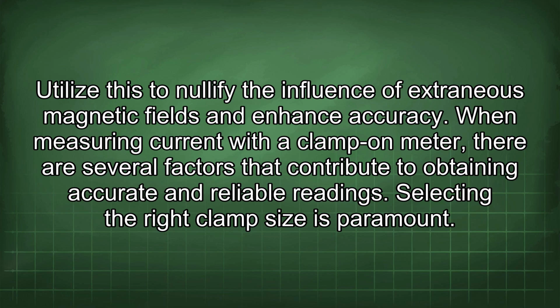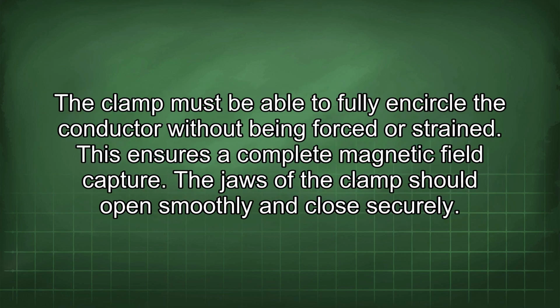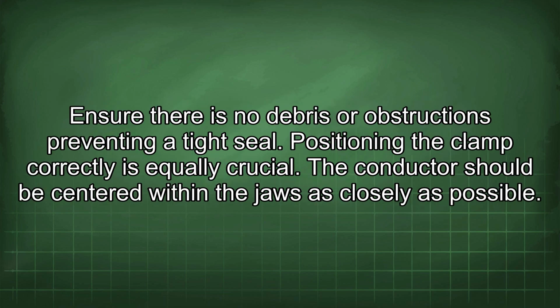When measuring current with a clamp-on meter, there are several factors that contribute to obtaining accurate and reliable readings. Selecting the right clamp size is paramount. The clamp must be able to fully encircle the conductor without being forced or strained. This ensures a complete magnetic field capture. The jaws of the clamp should open smoothly and close securely. Ensure there is no debris or obstructions preventing a tight seal.